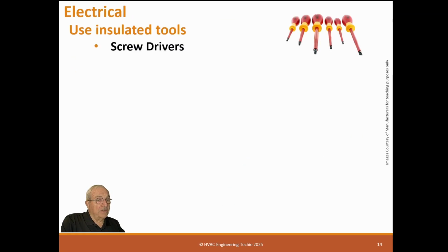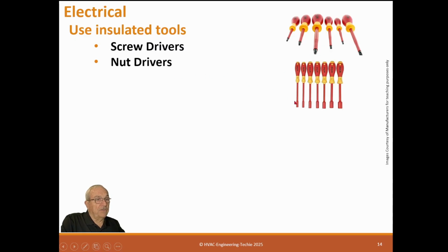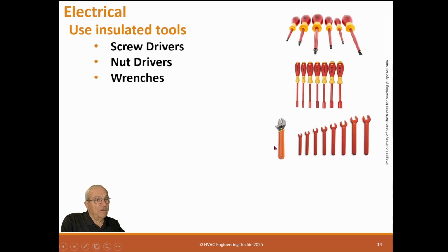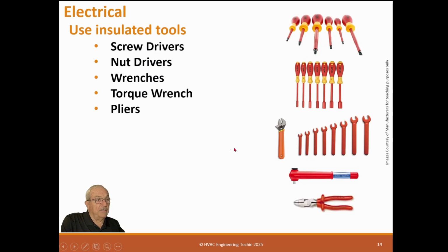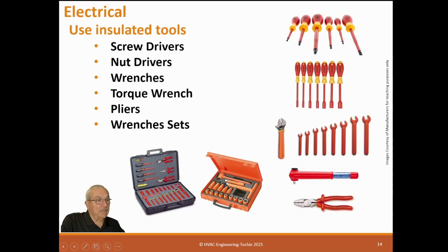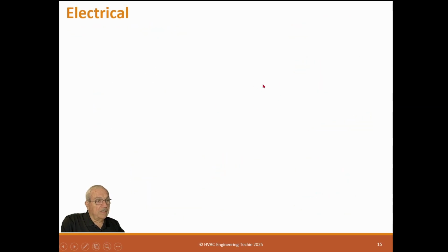Use insulated tools. They have screwdrivers. You can see they're insulated clear down to the shaft. Nut drivers that are insulated the same. Wrenches that are all insulated. Even crescent wrenches that are insulated. Torque wrenches that are insulated. Pliers that are insulated. And then we have wrench sets that have entire sets of them insulated. What this is intended to do is, if you're on a bolted connection, you don't just happen to touch the other connection, because you're insulated from it. So that's very important to use these.